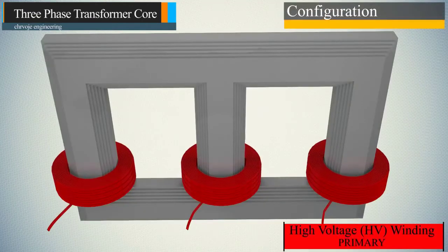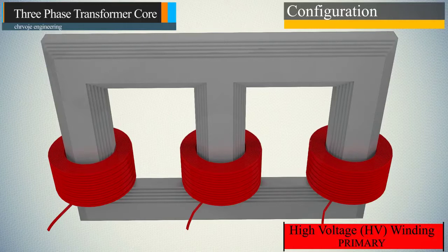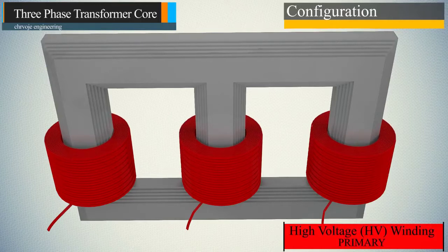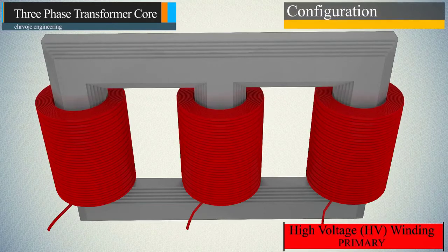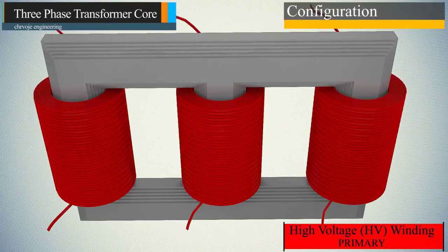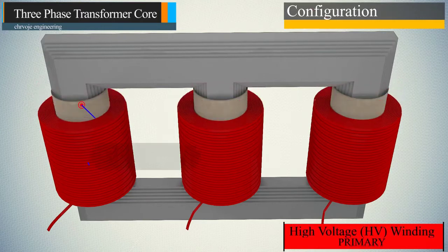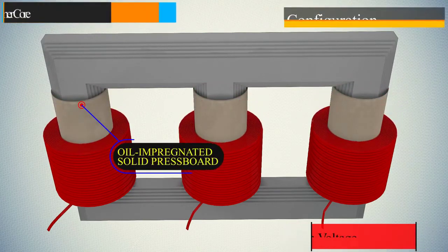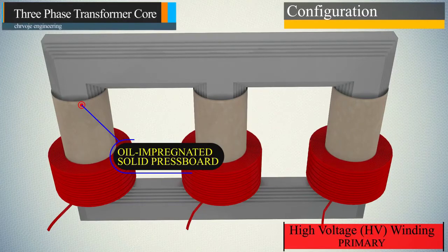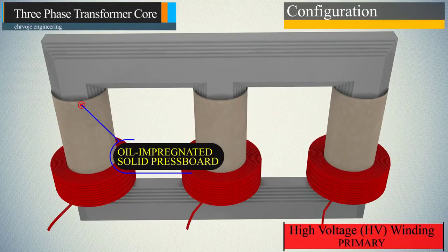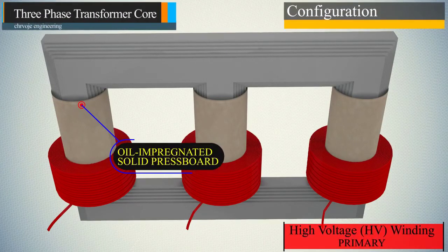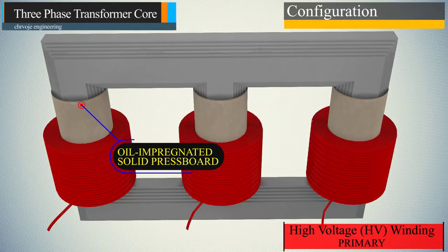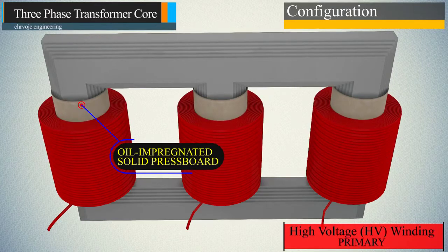First winding near core is primary winding, and this winding sits concentrically around the limb. In case the step-down transformer primary winding is high voltage winding. In most cases, insulation between primary high voltage winding and magnetic core is some kind of oil-impregnated solid pressboard. The main function of this insulation is to prevent physical contact between the core and windings and to prevent mechanical stress developed in winding, which has crushing force on core material.